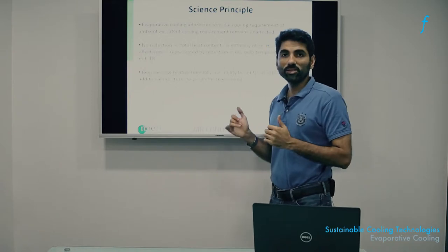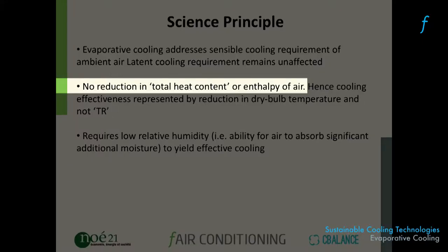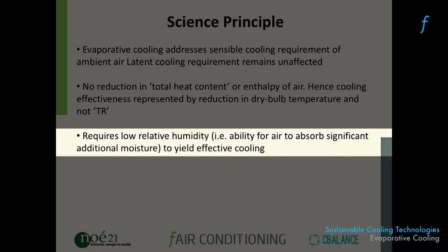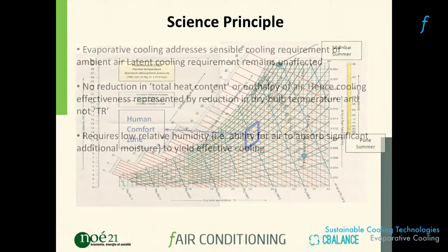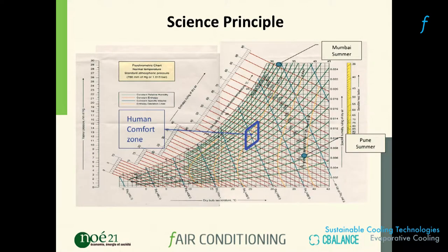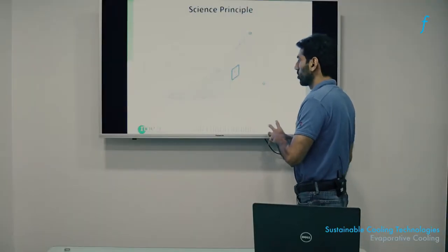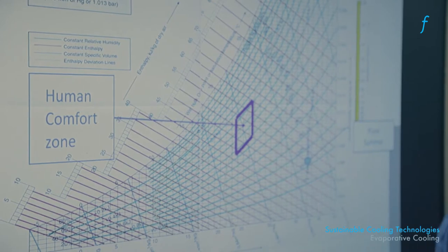There is a very palpable and verifiable cooling effect because the temperature of the air does drop, and we will see how this plays out in terms of psychrometry. These technologies work well only when outside air is relatively dry and ready to absorb adequate moisture. They do not work well in places with high humidity — you need dry air for this technology to work well. On the psychrometric chart, this constraint of needing dry air is clearly visible.